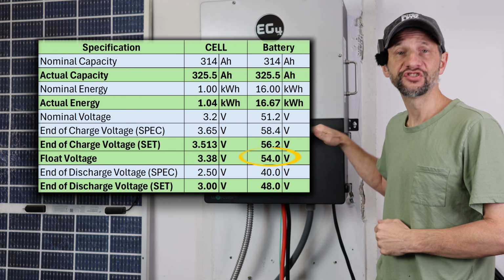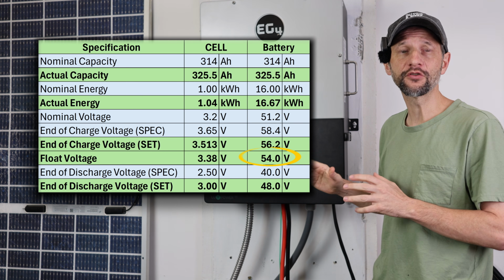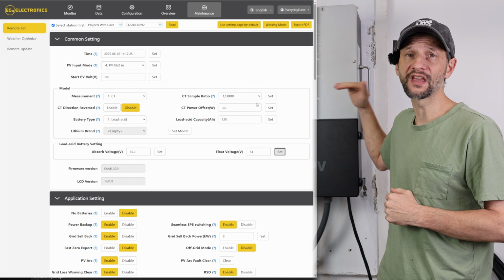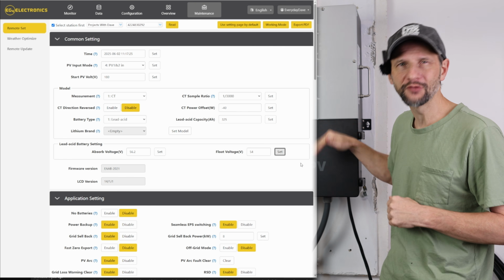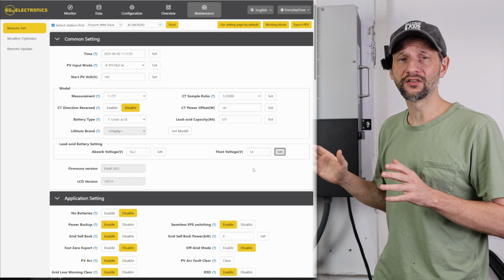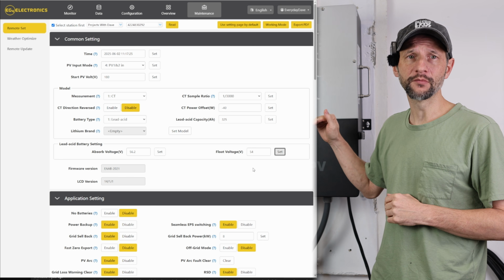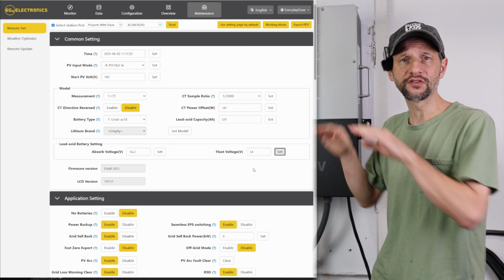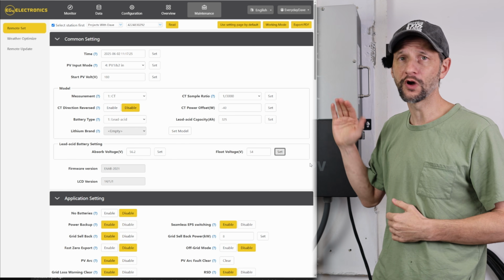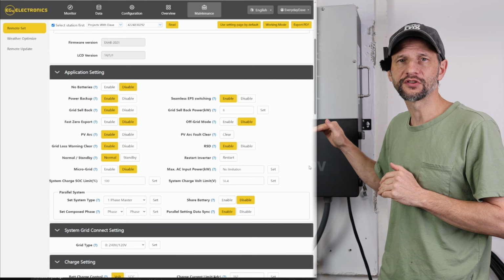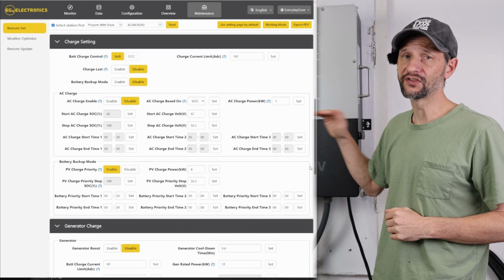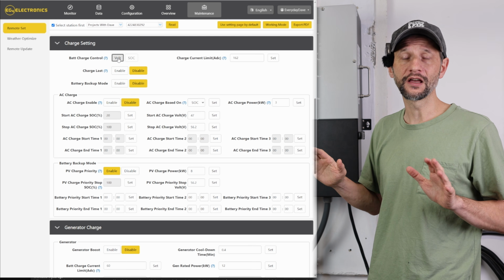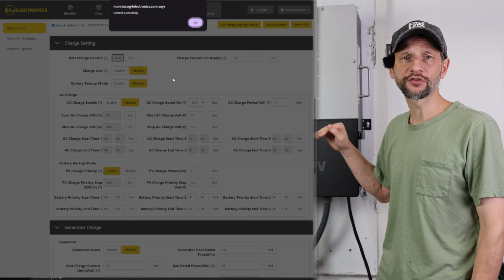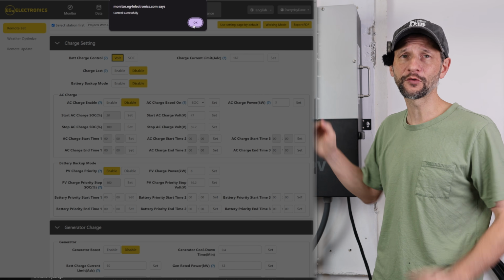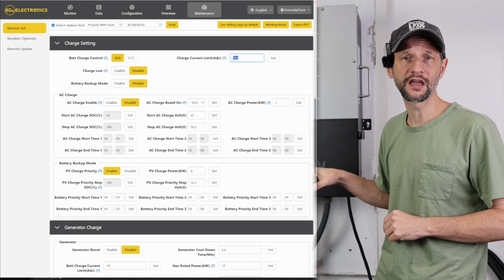We set the float voltage to 54 volts so that once the battery is fully charged, it won't hold it at that higher voltage or constantly run a charge cycle. That's still above the balance voltage set in the BMS, so if any cells are mismatched, the BMS can continue to balance them while it's floating. Dropping down to the charge settings, we'll be using voltage instead of state of charge, since we don't have communication. I set the charge current limit to 162 amps, which is about 0.5 C for these batteries.